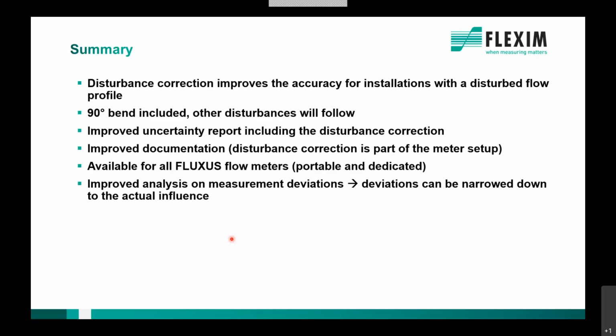That means disturbances, either 3 or 4 or 5%, depending on the diameter straight length, have always created an under-reading in the flow. Only for longer straight lengths and for certain disturbances do we have an over-reading, but mostly an under-reading. So using a disturbance correction will make the reading always more accurate than not using any disturbance correction. So even if you have something like a 90-degree bend or double bend out of plane, use that function because it makes the reading better instead of not using it at all.